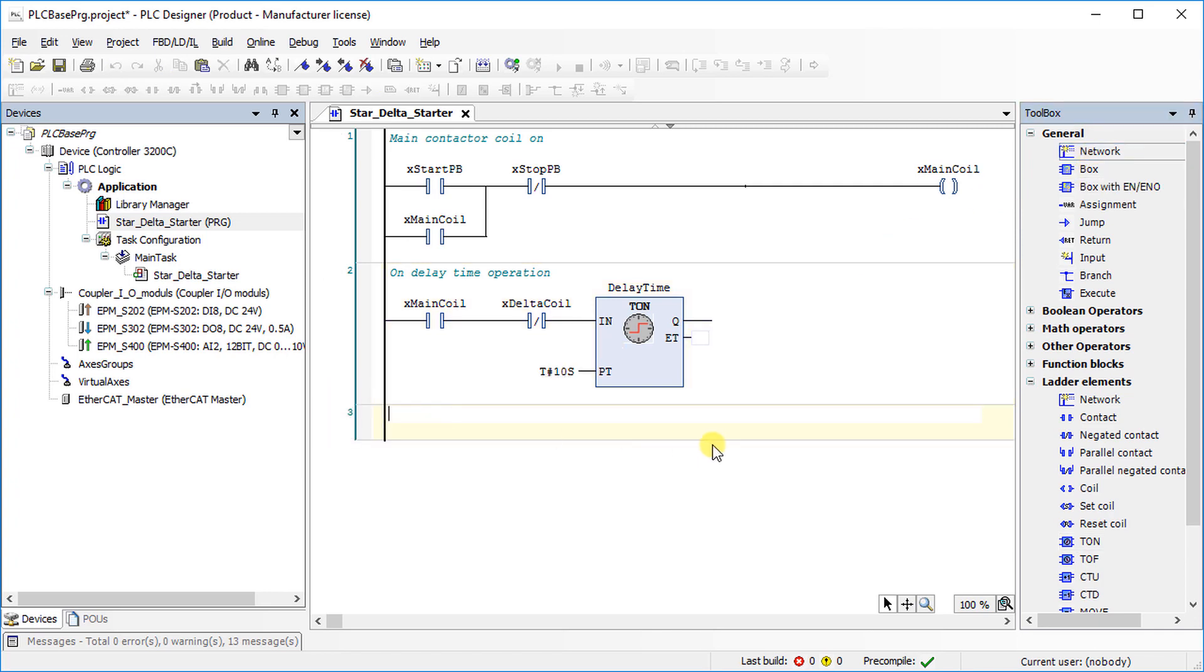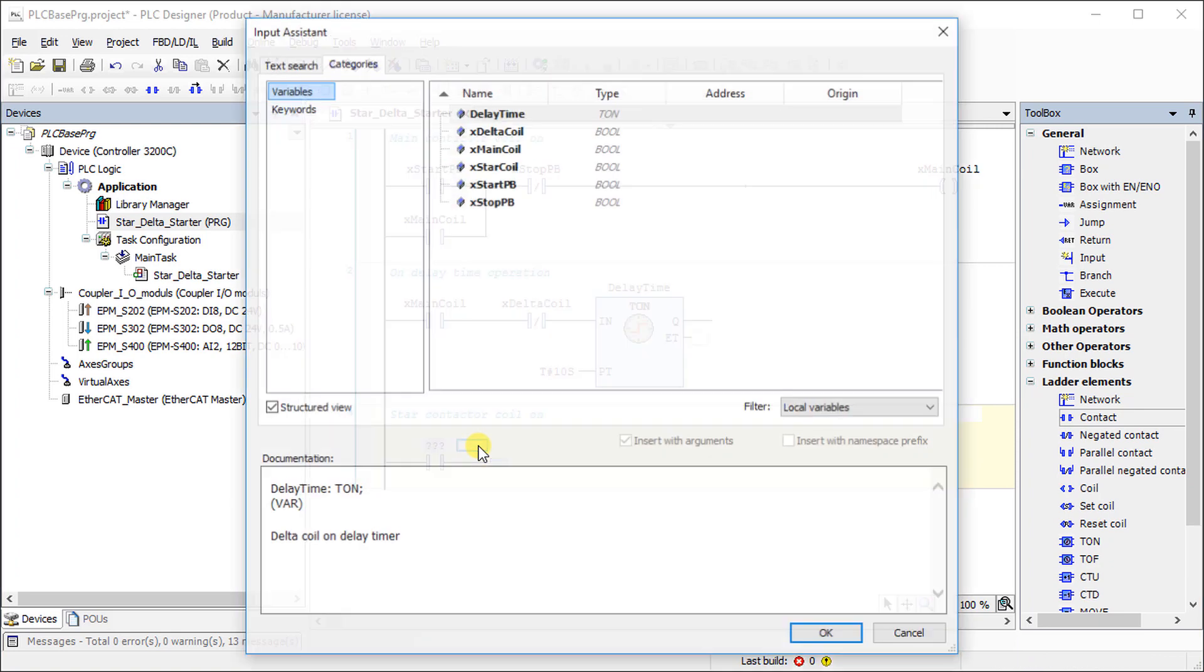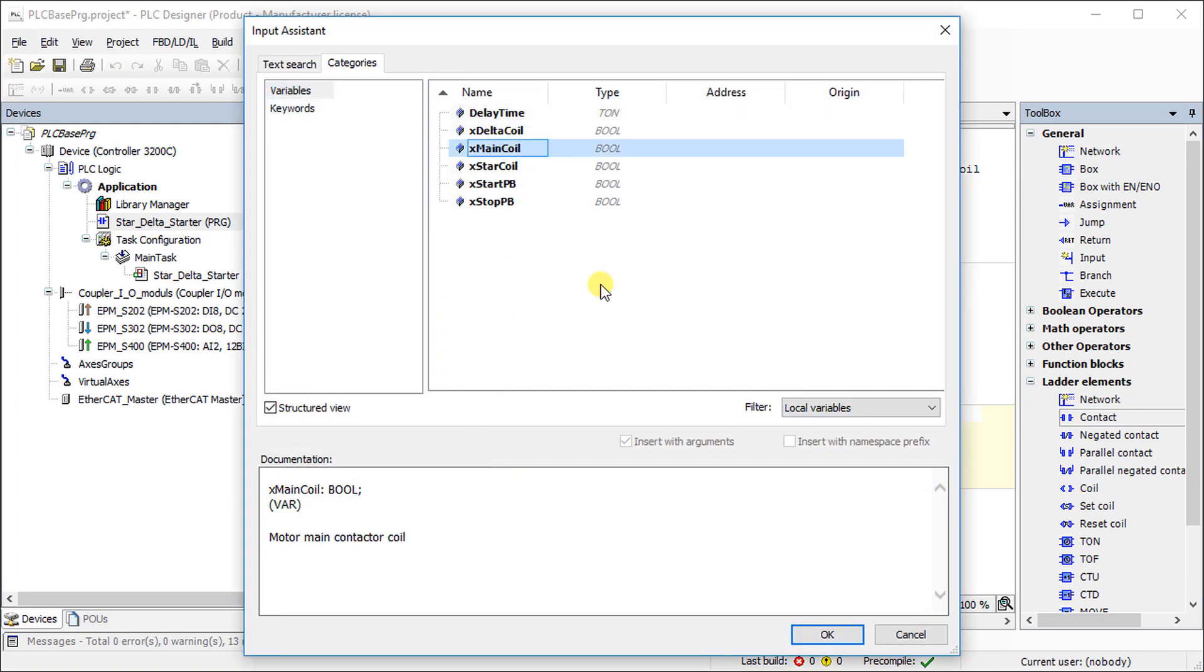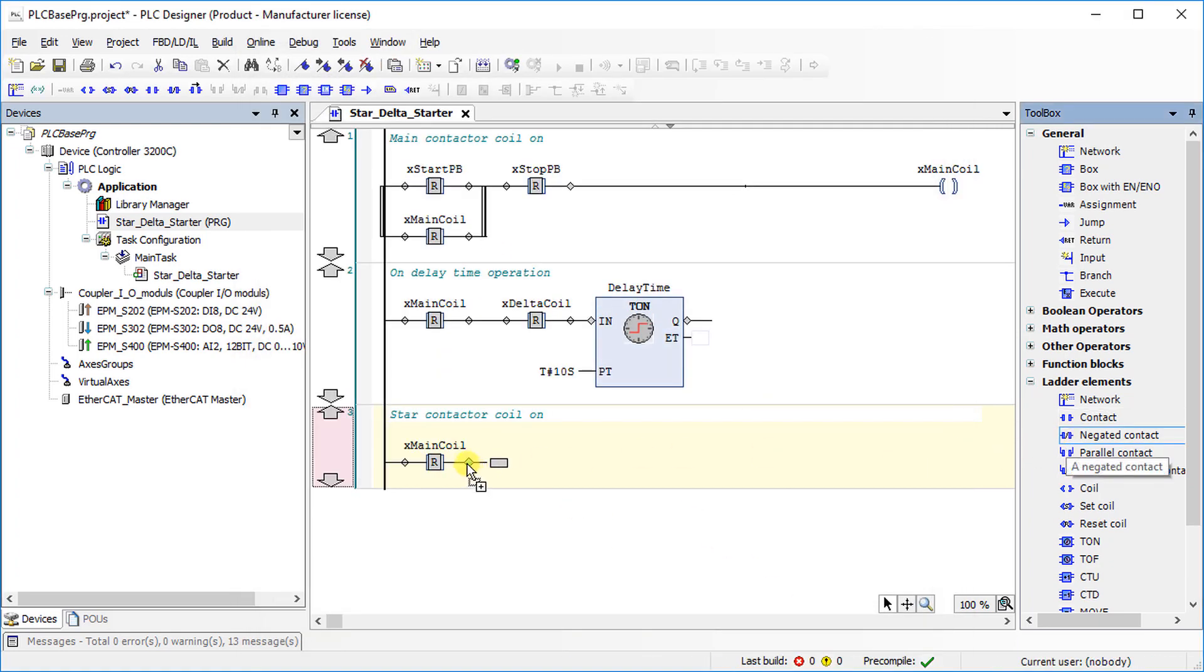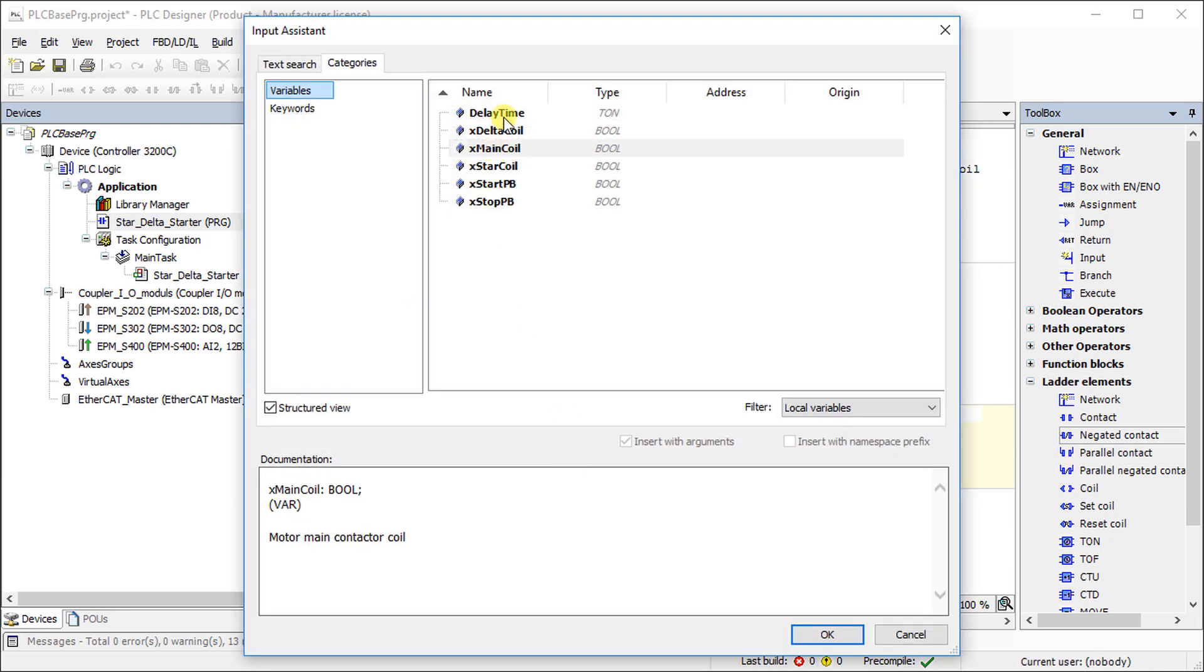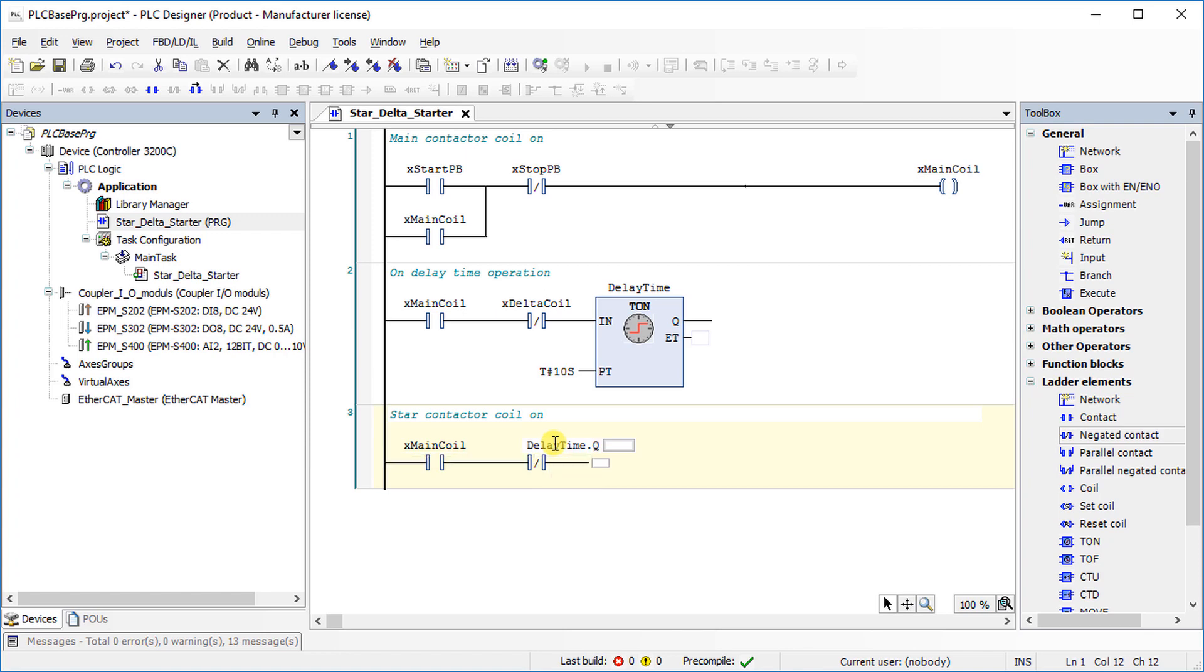Program the logic of star coil. This coil turns on as soon as the main coil is turned on. It turns off after the delay time is over. Make sure when delta coil is on, star coil should not energize in any condition or vice versa.